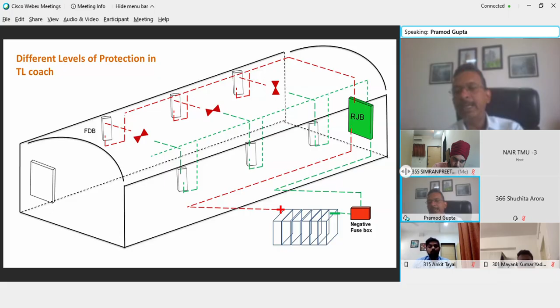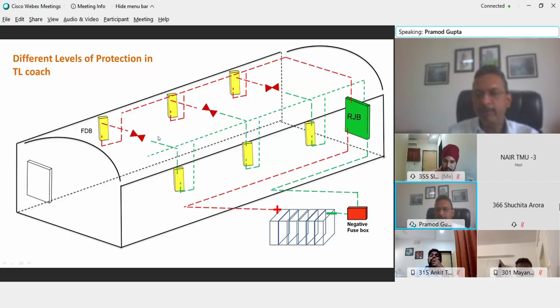The third level of protection is the simplest, a fuse distribution board that takes care of the earth fault in a particular branch. So we have three levels of protection, and depending on the severity of the fault, one of these protection systems becomes activated and gives an indication to the maintenance staff as to where to attack and how to remove the earth fault or problem in the circuit. This is how different levels of protection are provided in a coach.